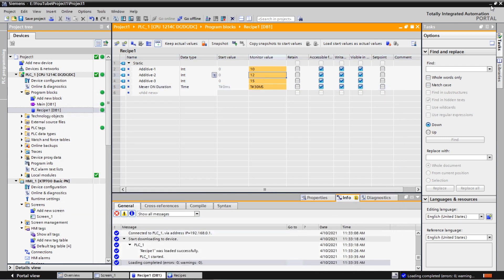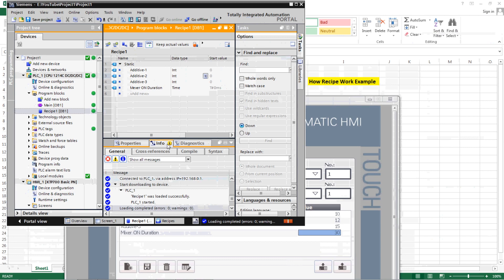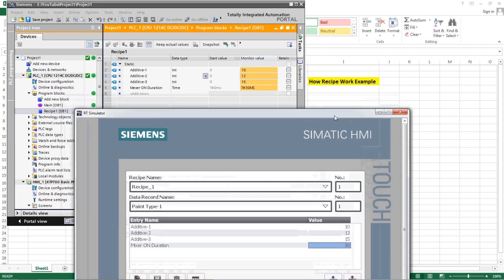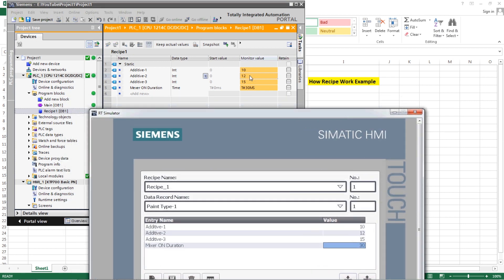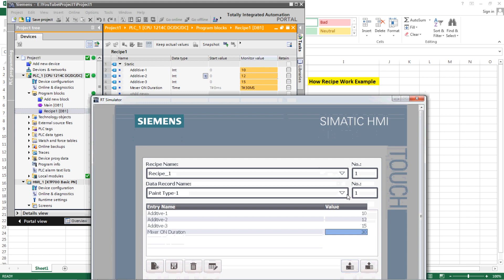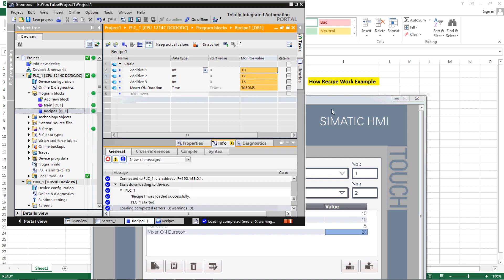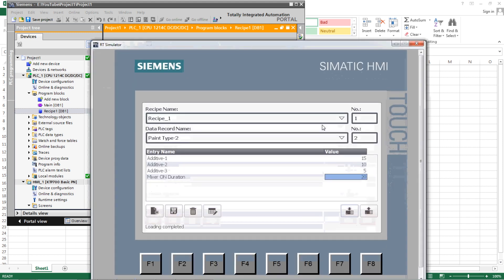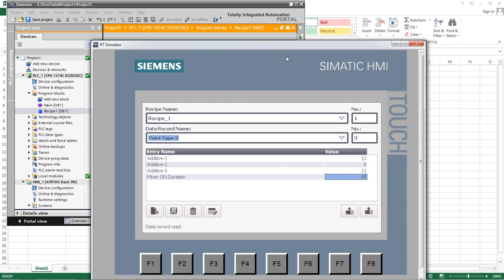Let me rearrange the window. You can see here the values 10, 12, 15. Now suppose we select paint type 2 — the values shown in the recipe view change. But the PLC still has the first recipe values, so again you need to press Download to push the new values into the PLC. Similarly, if you select the third one and press Download, those values get reflected into the PLC.